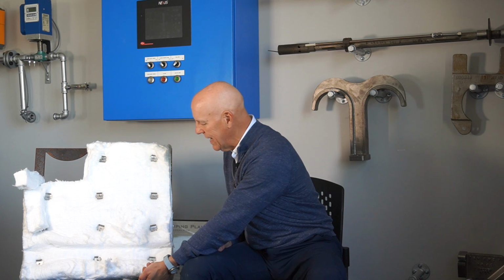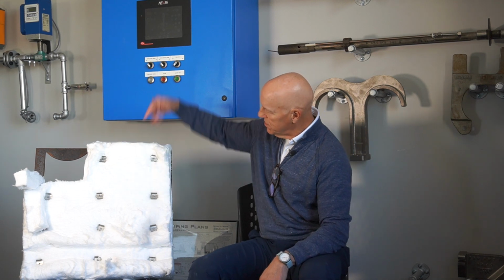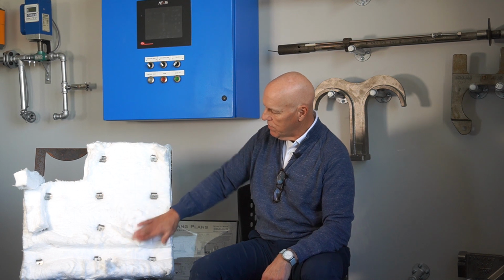So you have to be careful in your velocities, high velocity areas, in making sure that you're not going to exceed a velocity that could rip this up. Typically, in the 70 to 80 feet a second, less than that, you're going to be okay. Now, I don't know if you can see it, but also how you lay this out relative to the gas flow makes a difference. You see there's a joint here because you have to overlap the joints. Well, obviously, if the gases are flowing this way, it would get underneath that joint and tend to pull it off. So you want to orient your burner and your flue gas flow such that the gases would flow this way, so when you overlap your joint, it's not trying to rip that joint apart.